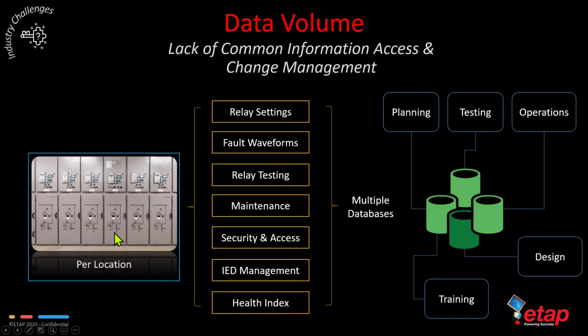When you look at each location and each device, you can essentially have various parameters such as relay settings, fault waveforms, relay testing data, maintenance records, security and access control, IED management and configuration data, and of course the health index of each and every asset in the network. And this is typically saved in multiple databases that is consumed by multiple departments such as planning, testing, operations, design, and even training. So therefore there's a lack of common information access and of course a change management system to manage this data across the board.